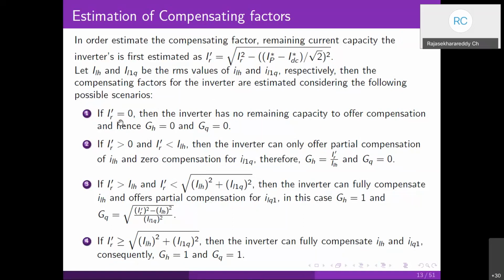So let's see, if IR equals 0, that means we don't have any capacity. That means the inverter is fully loaded, so it is not available for ancillary services such as harmonic and reactive current compensation. Therefore we set GH and GQ equal to 0. In the second case, if the remaining current capacity is greater than 0 but less than the RMS value of the harmonic currents, then the inverter can offer partial compensation of the harmonic currents and zero compensation of reactive currents. So we make GQ equal to 0 and GH equal to IR prime over ILH.